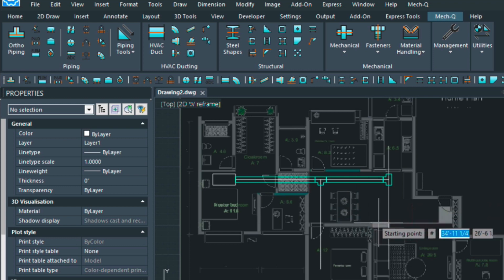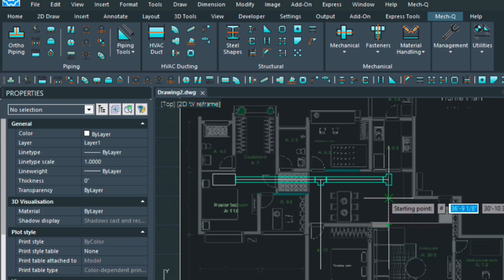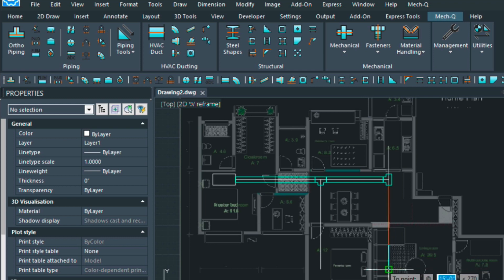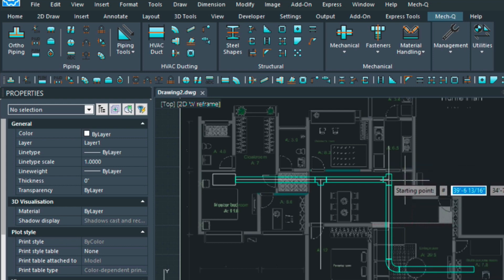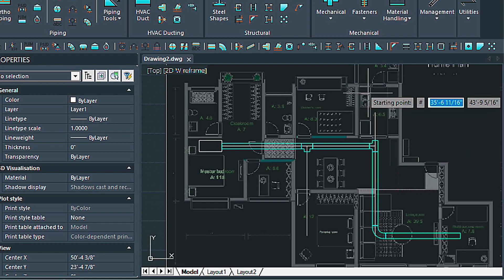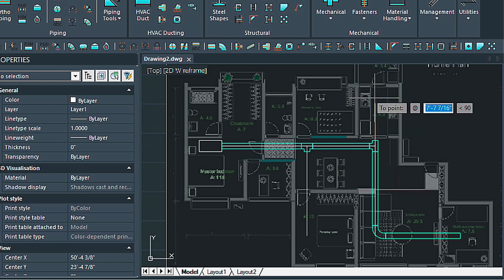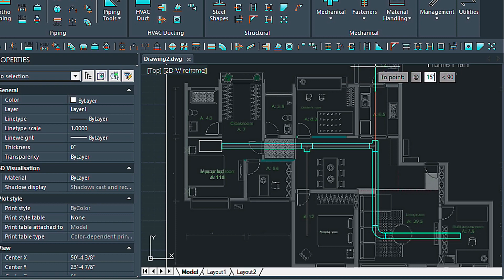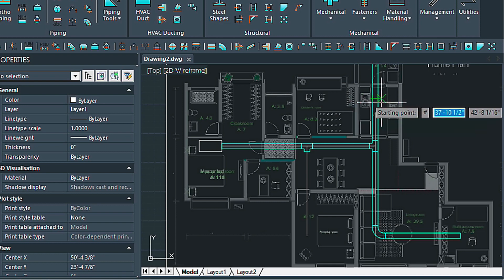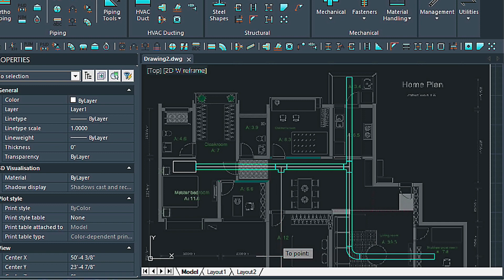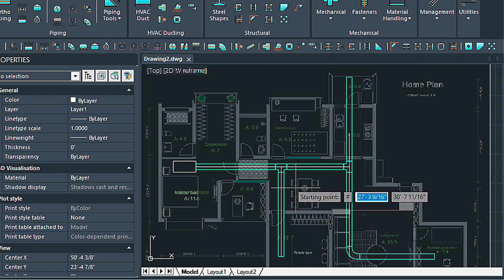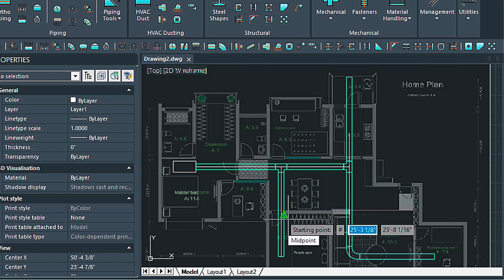The nice thing about the run command is if you have a turn, it will put the elbow in automatically — we'll demonstrate that here. Starting here, left clicking, and now let's go over 15 feet — just type in 15 feet — and then press Enter to complete that piece. If you don't press Enter you're not going to get that last piece in; the Enter command is just telling Mech-Q that you're done with the run. Let's put in a couple more pieces, pressing Enter each time after we're done.